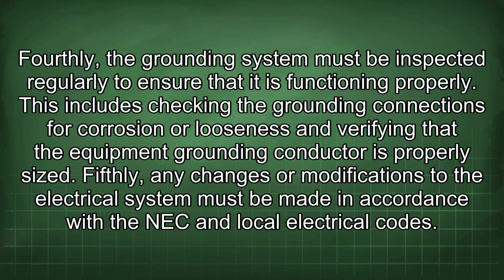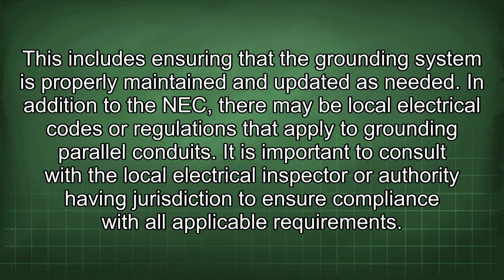Fourthly, the grounding system must be inspected regularly to ensure that it is functioning properly. This includes checking the grounding connections for corrosion or looseness and verifying that the equipment grounding conductor is properly sized. Fifthly, any changes or modifications to the electrical system must be made in accordance with the NEC and local electrical codes. This includes ensuring that the grounding system is properly maintained and updated as needed.